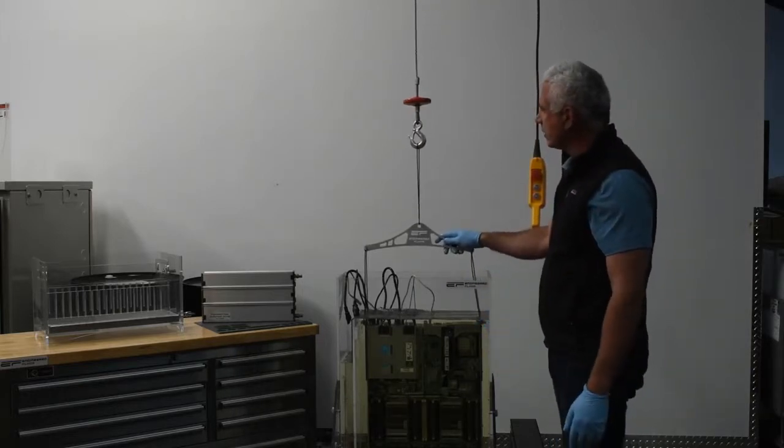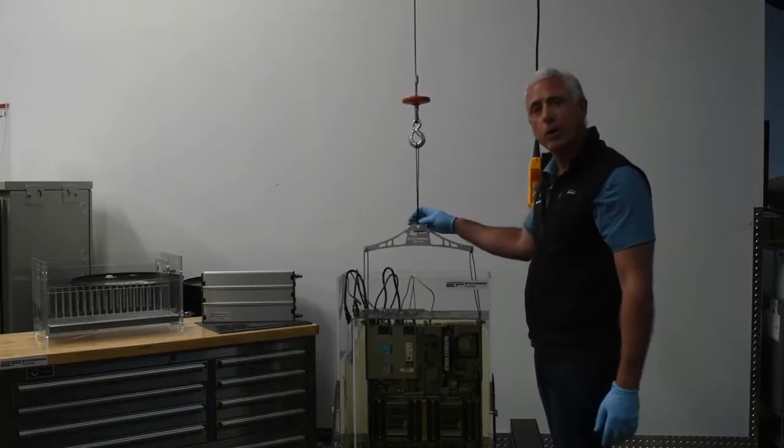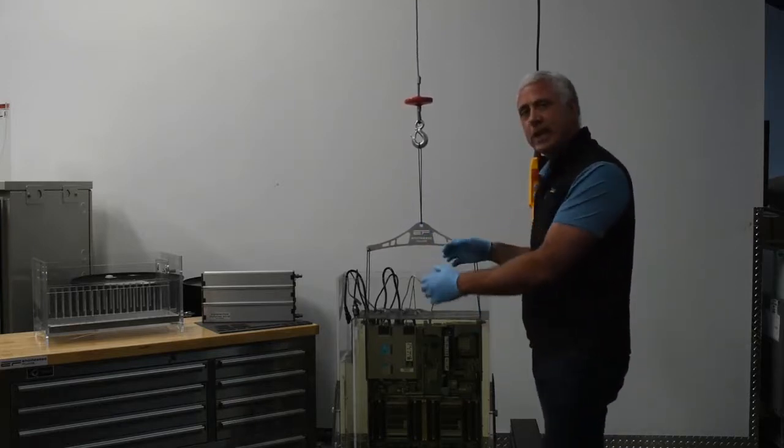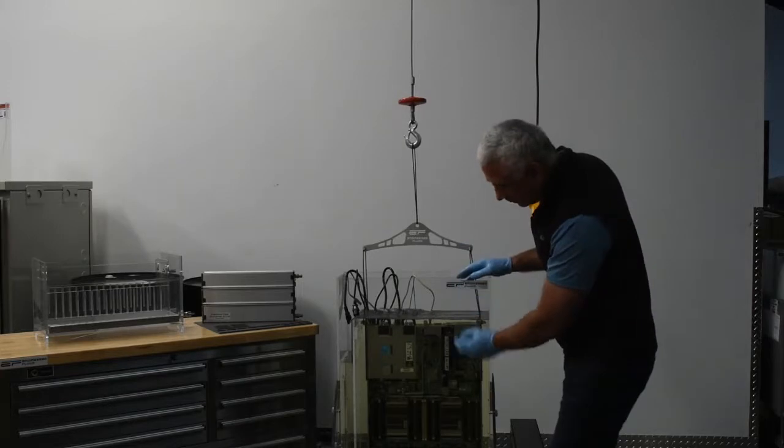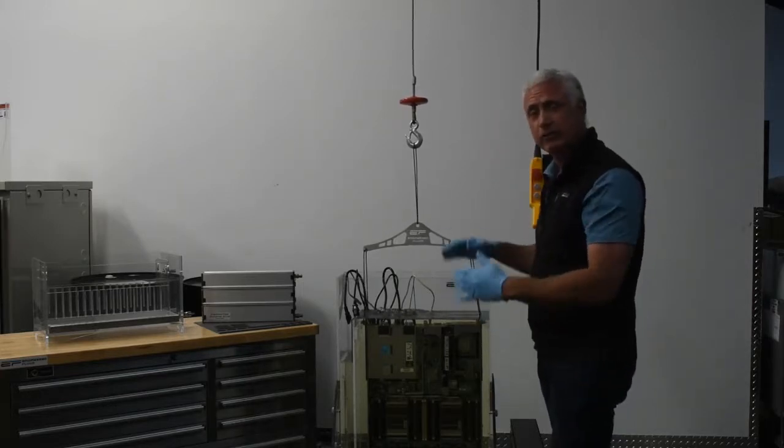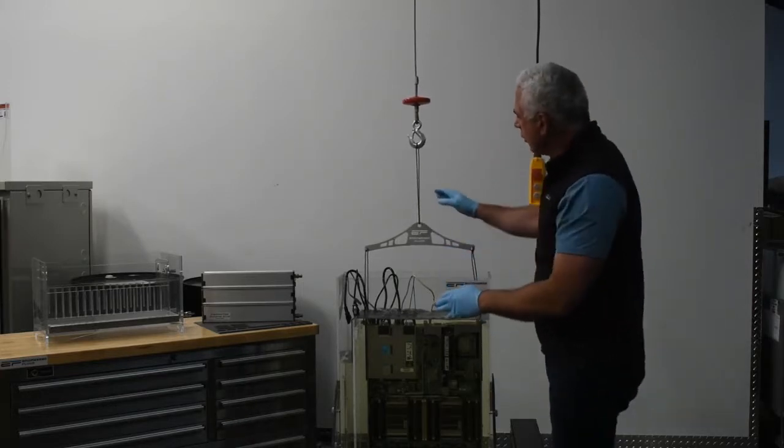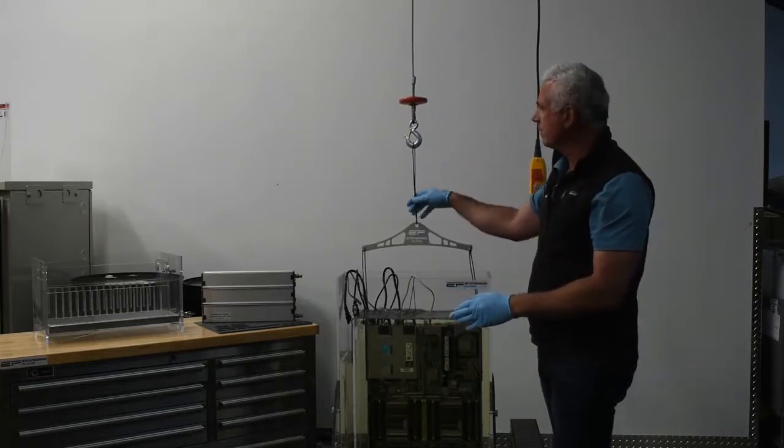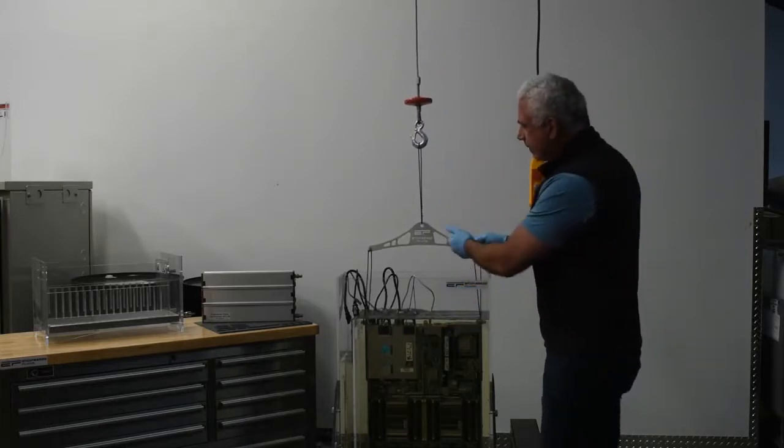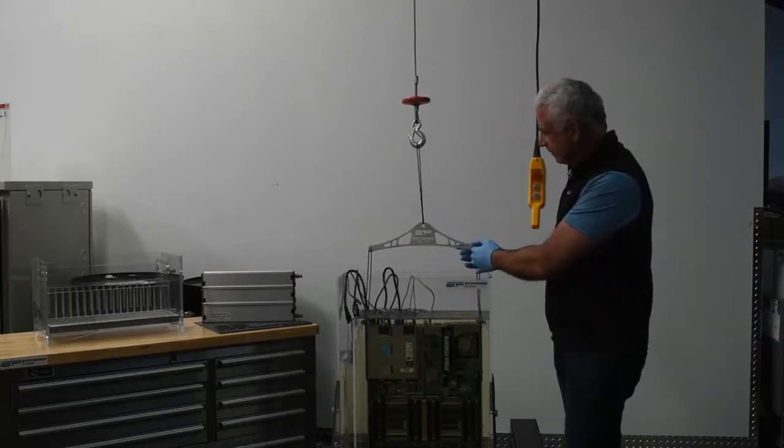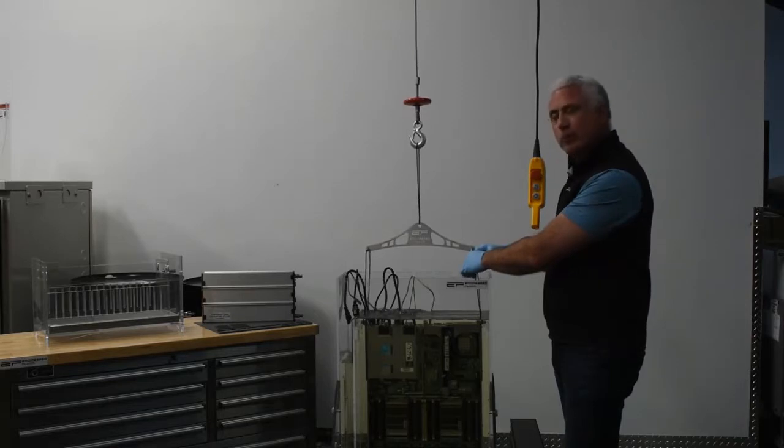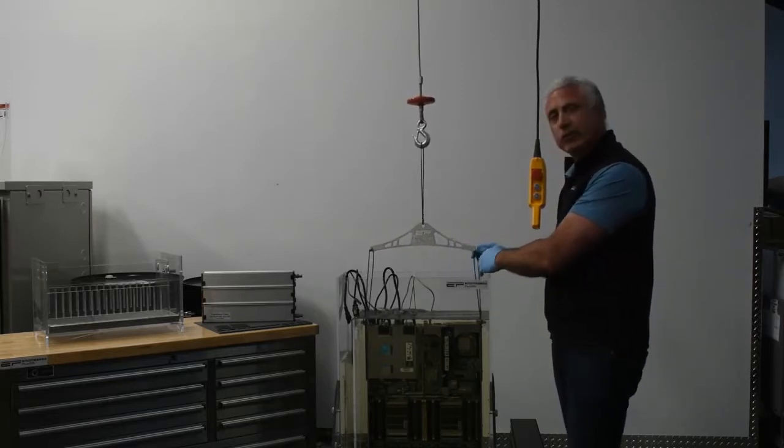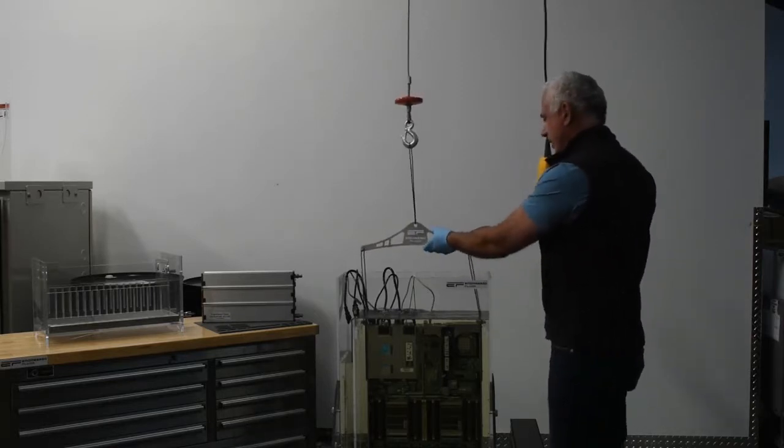So in order to do that we always recommend the use of a hoist. This is significantly easier than reaching in and trying to manhandle the server, particularly because these particular types of 1U servers are very long. So the hoist is quite simple. We have an overhead gantry with a lightweight crane and typically we like to use just a simple lift hoist like this and then we use some simple loops. And I'll show you how we attach the loops to the server as we bring it out.